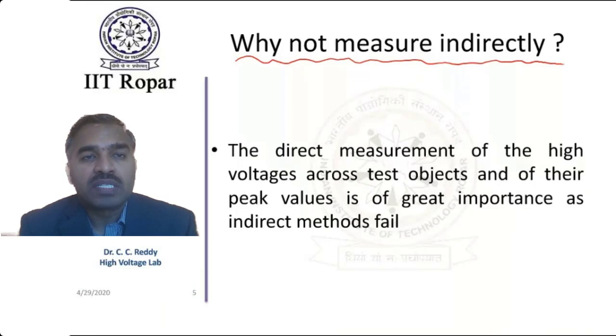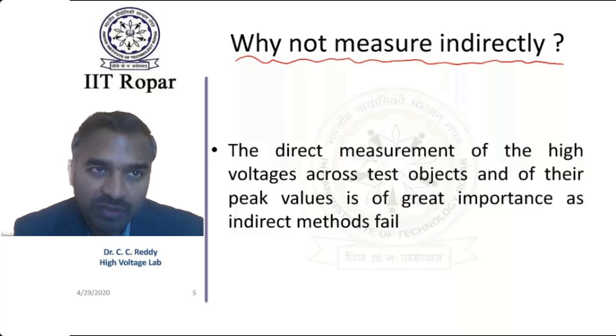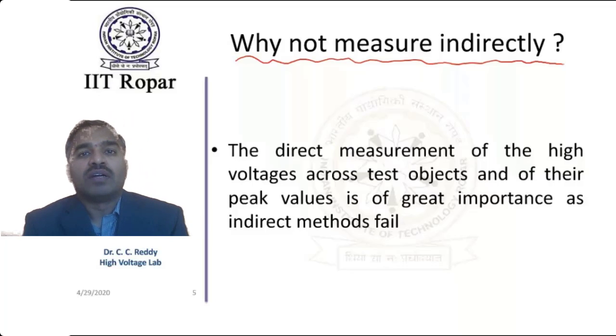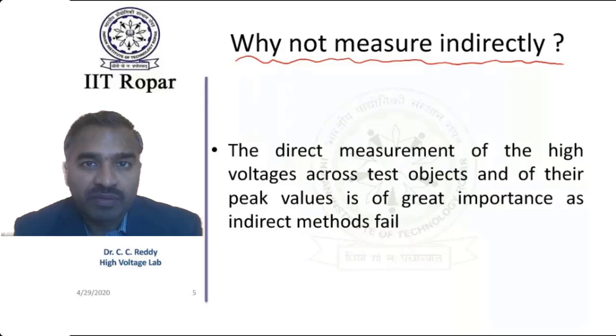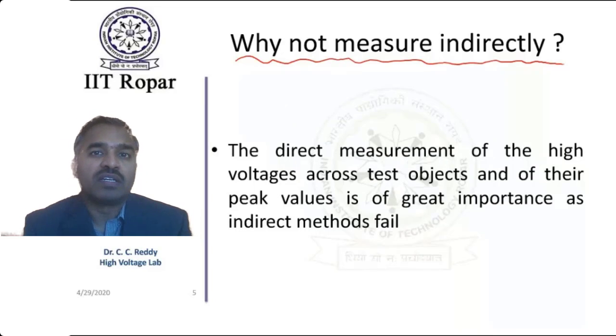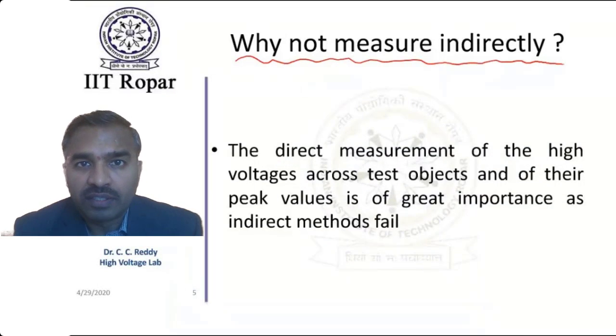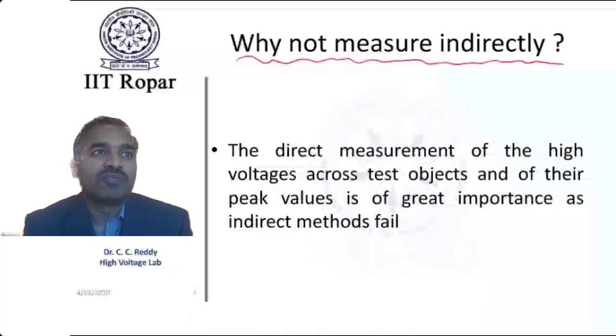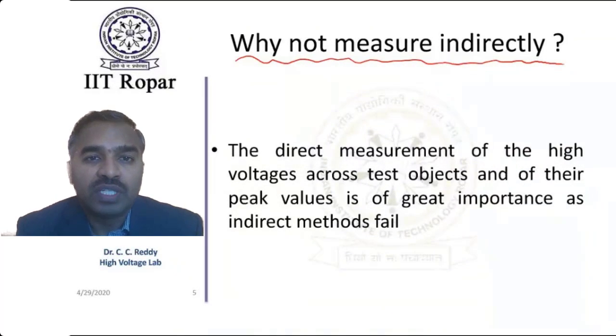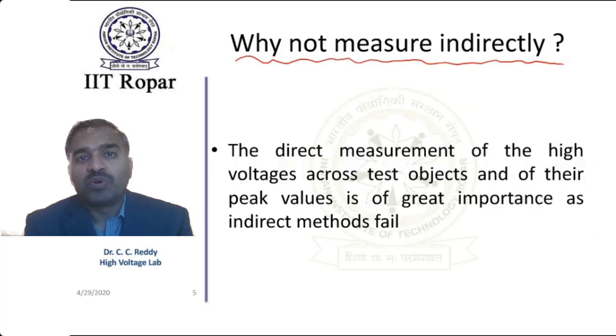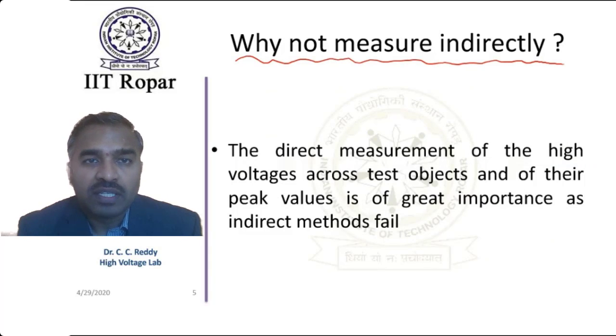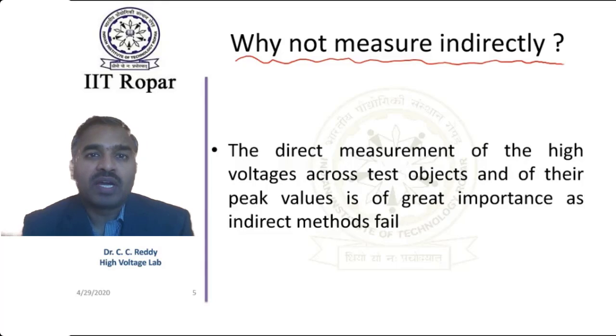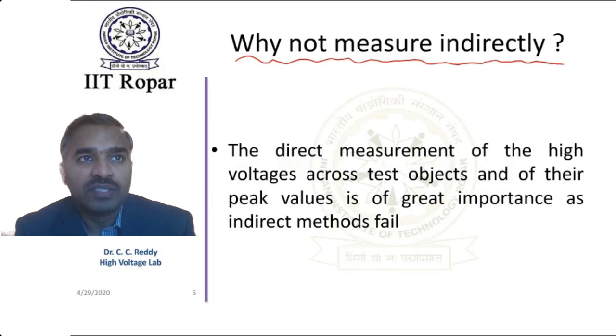Yes, because of the internal impedance of the transformer itself, as well as the impedance of the load, and the connecting lead resistance also comes into the picture, though that is small. Due to these effects, the output voltage is not exactly the same as the input voltage multiplied by the turns ratio. Therefore, we cannot do indirect measurements in the AC case.